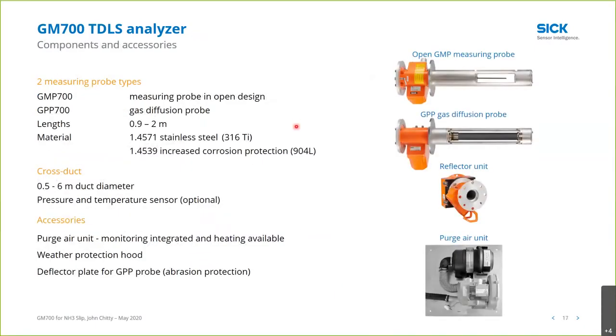So we have two different types of probes available. The first one is the GMP, which is a gas measuring probe. It has an open path. That stinger you see is actually an RTD to measure temperature. So the open path probe is typically what we use in ammonia because ammonia is very sticky.